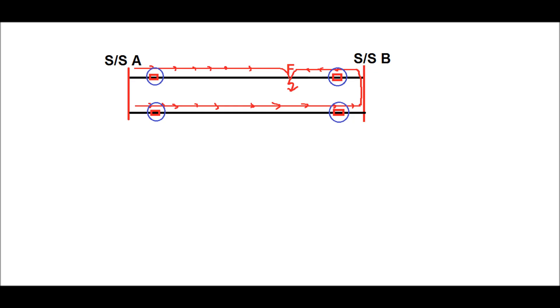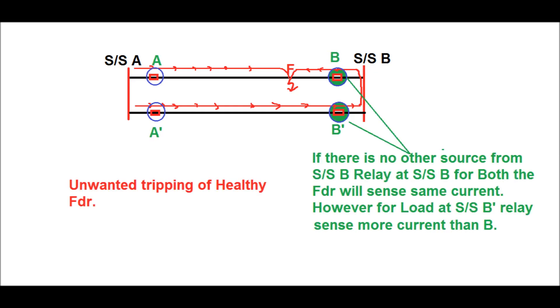A fault occurs at a point very close to substation B. The fault current will flow as shown in this diagram. Now if there is no other source from substation B, the relay at substation B for both feeders will sense the same current. However, for the load at substation B', the relay senses more current than substation B.